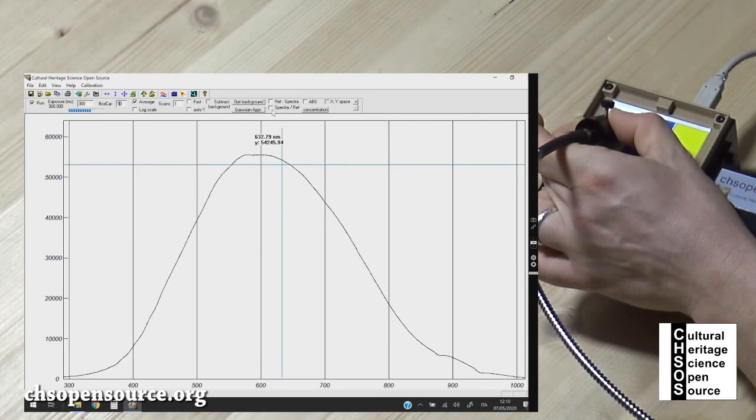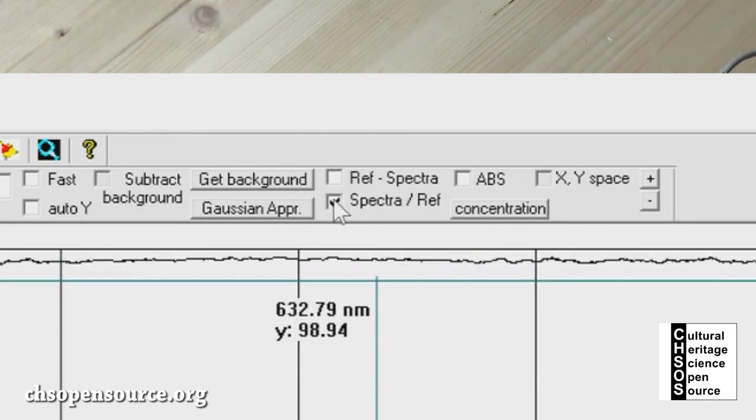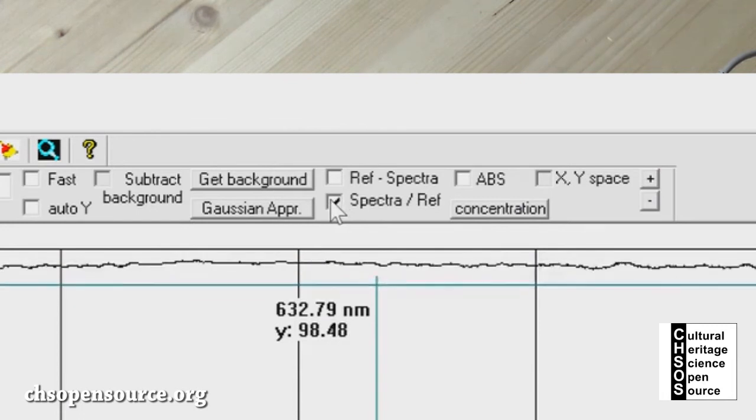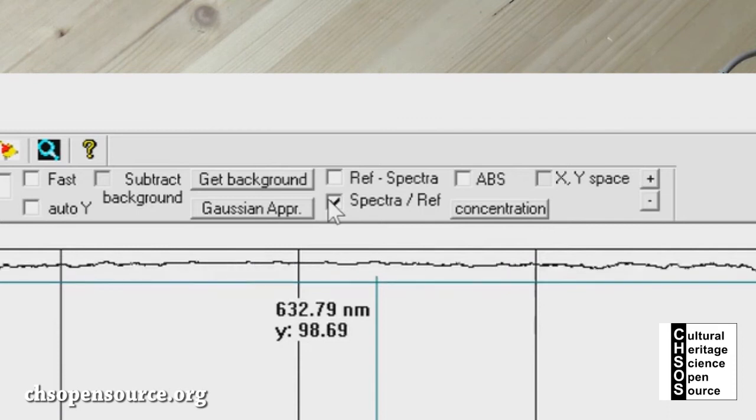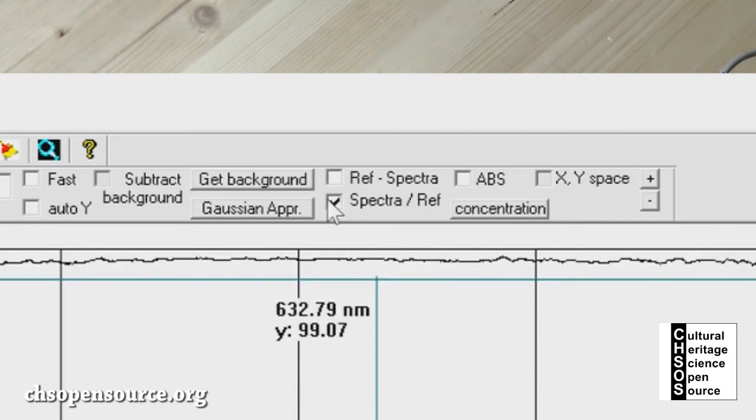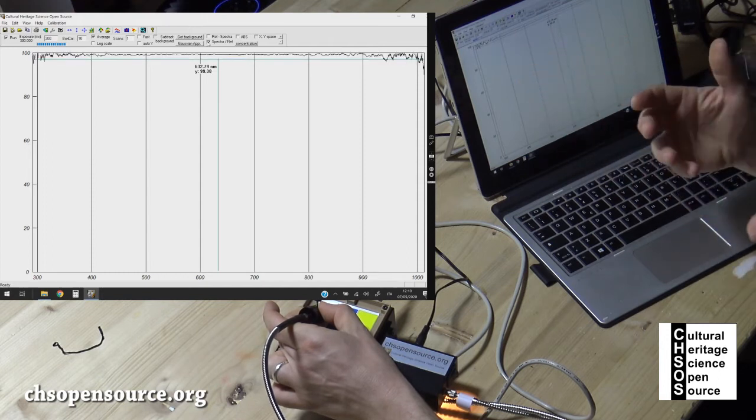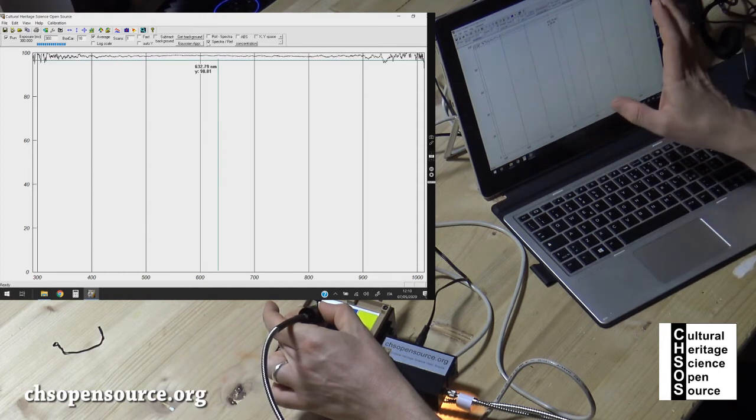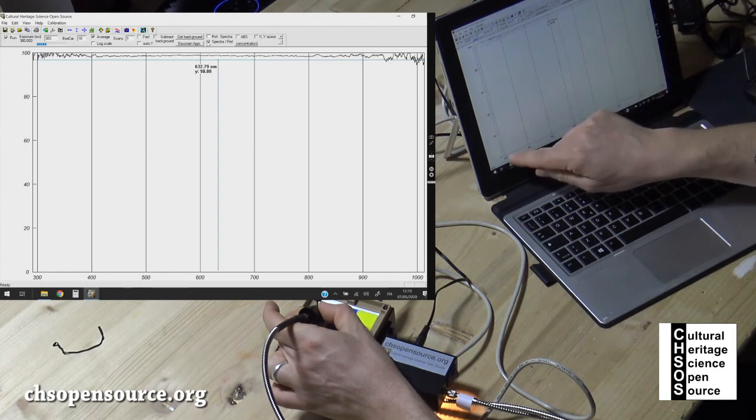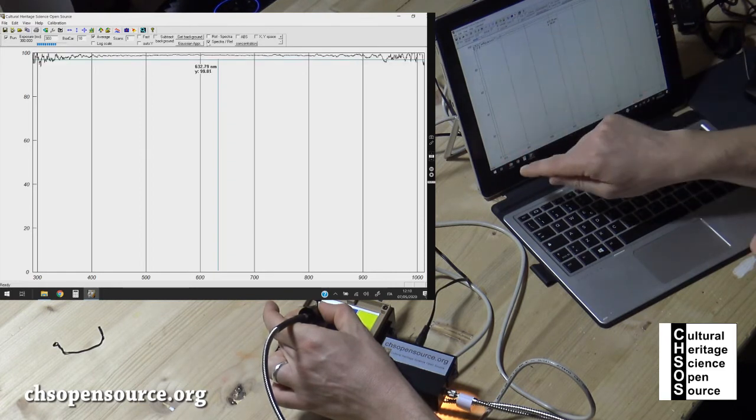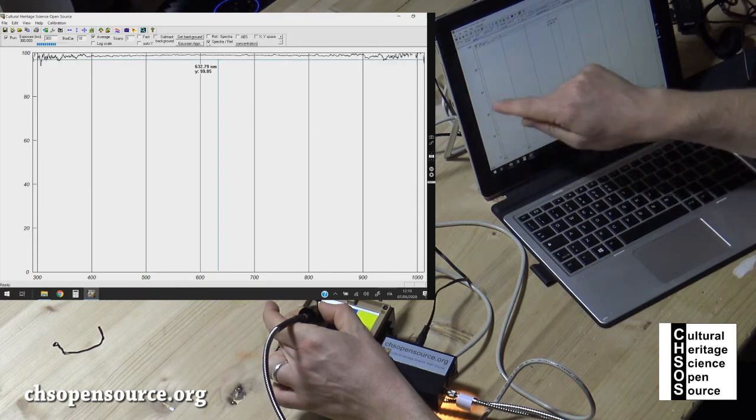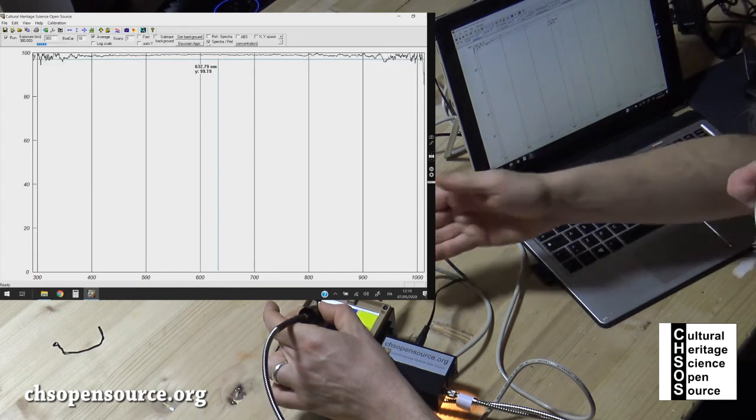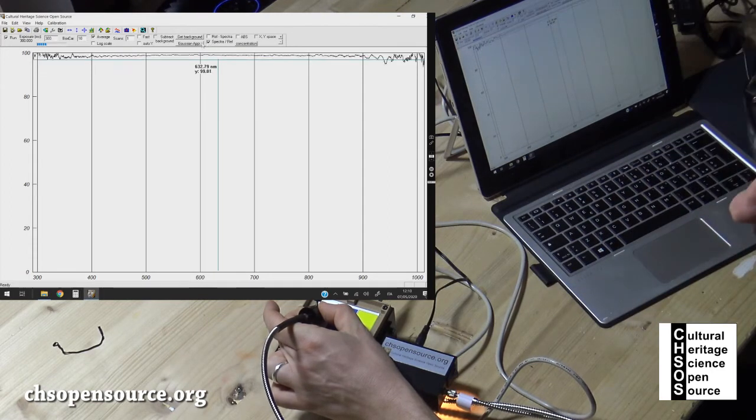In general you want to wait about five minutes for the lamp to reach the standard temperature and stabilize the lamp. We consider we already passed the five minutes. To do the calibration you need to click this rainbow icon over here. The name is 'get source spectra'. I click it and nothing happens over here but the calibration has been done.